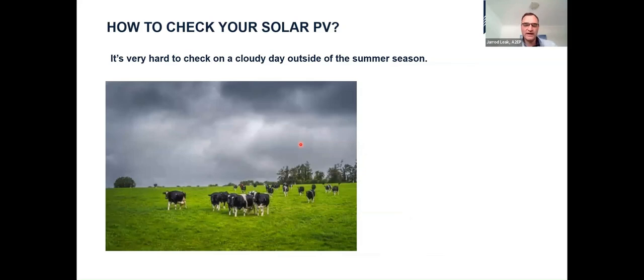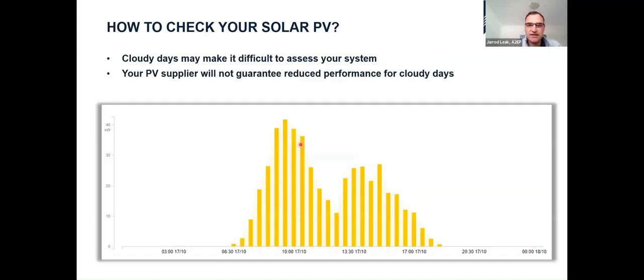Next thing to consider is how you check the performance. I mentioned before about poor connections and installation errors. On a cloudy winter's day it's very difficult to tell if the performance is meeting expectations. This is from a 60 kilowatt system - it's 40 kilowatts in the morning, and by the middle of the day you're down to only 10 kilowatts as the clouds come over. So looking at it like this, it's not easy to assess whether you're getting the right performance and everything's connected up correctly.